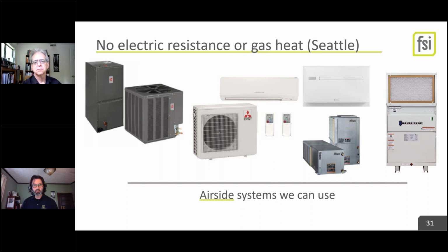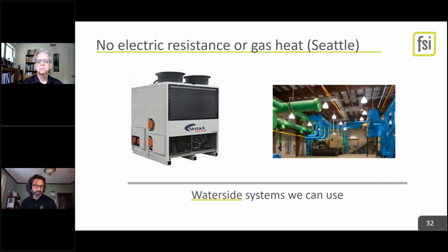I actually added the water source heat pump, that little galvanized looking box on the lower right. You can use these systems. They're all heat pump based. Great, pretty normal. And then let's go to the next slide. You can also use hydronic systems. We already talked about it. On the left there is that heat pump chiller or air to water heat pump, depending on the firm and the exact manufacturer. It's literally the same thing. On the right is a centrifugal chiller plant set up to do heat exchange for a 4-pipe system, but it's the same idea. It's moving heat around and rejecting heat out when appropriate, pulling heat in when appropriate.